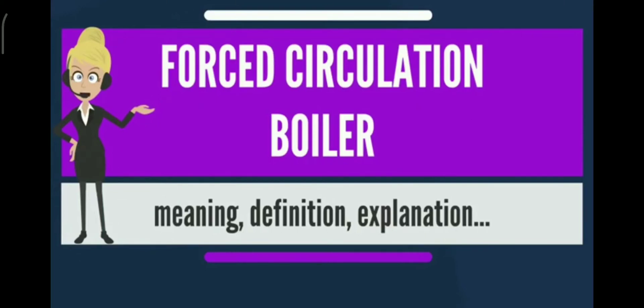A forced circulation boiler is a boiler where a pump is used to circulate water inside the boiler. This differs from a natural circulation boiler, which relies on density difference to circulate water inside the boiler. In some forced circulation boilers, the water is circulated at 20 times the rate of evaporation.